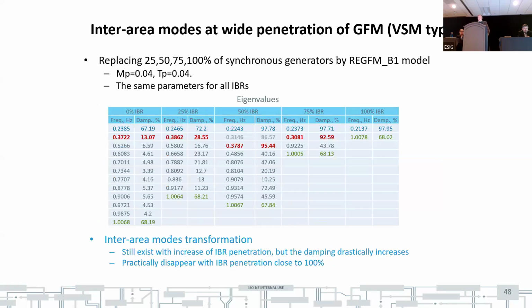So that slide shows what would happen with the dynamic properties of the system if grid forming inverters will replace 25, 50, 75% or 100% of generators. As you can see, the results are very optimistic. So what does it mean? That damping of all modes increased very significantly. And as soon as you approach 100% penetration, actually all oscillation disappeared.